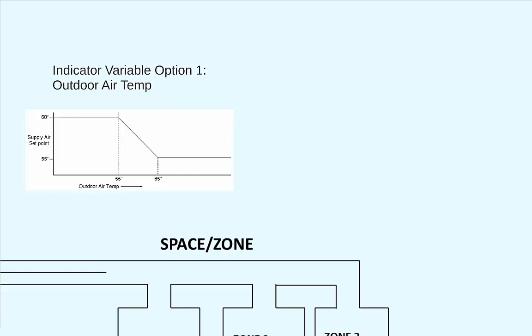This is becoming an old way of thinking, as many spaces in commercial buildings are dominated by internal heat gains from occupants, lighting, and equipment. That means that maybe a particular space would require heating on a Monday when it's 45 degrees outside. However, on Tuesday, with outdoor air temperature also at 45 degrees, the space might actually be requiring cooling due to an increase in occupants and an increased use of lighting and equipment.